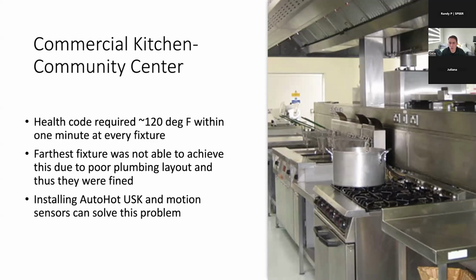So you can always install one of these under-sink retrofit type of pumps, of which there are many on the market. That way you can prime that dead leg branch line. Let's say you have a 40-foot, half-inch branch line coming off the circ loop, and it's still taking a minute or two to get the hot water there. This way you can install that secondary pump and get hot water at the end of any problematic branch line.